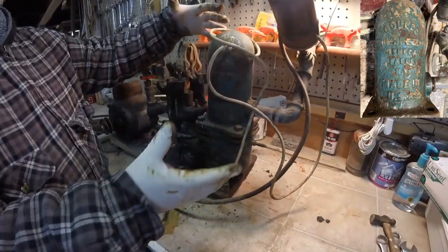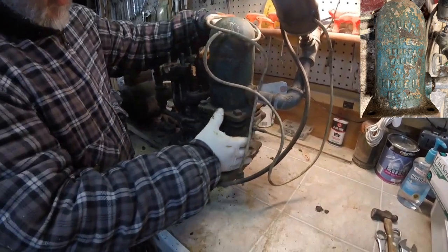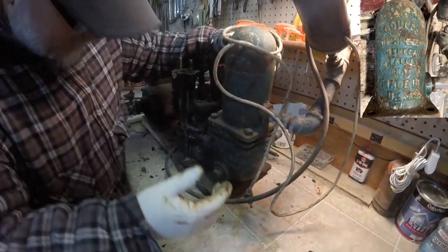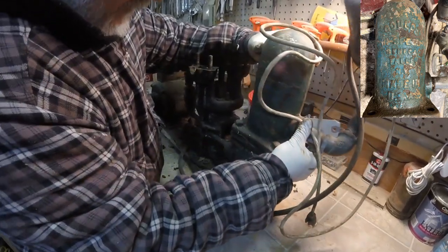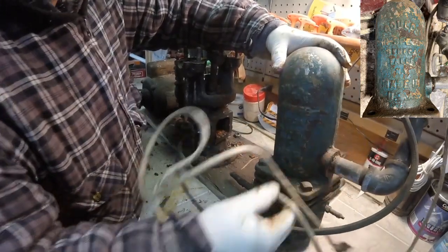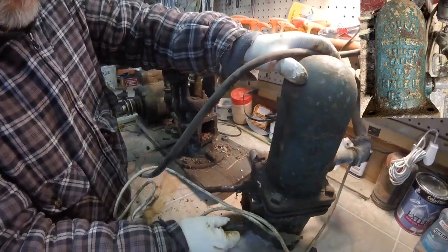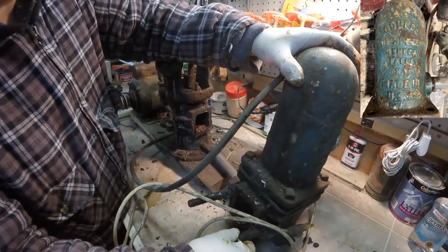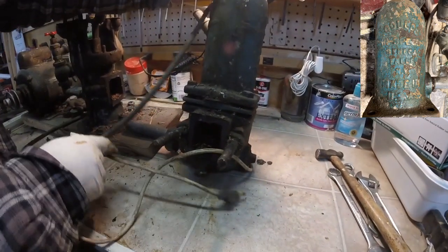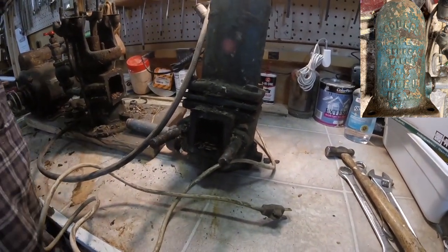Yeah, you see all this? Yep. Okay. Alright, so these 2 bolts are off. And what I'm going to try and do now is slide this piece out. Alright, I want to turn this around so we can maybe look inside and see what's going on. I'll get a little bit more light coming around here. Alrighty. That's why it won't pump water.